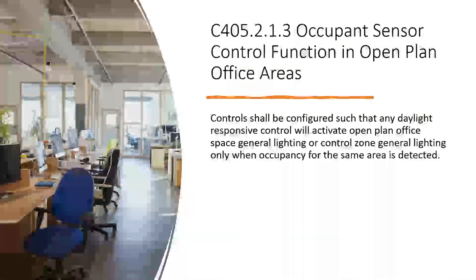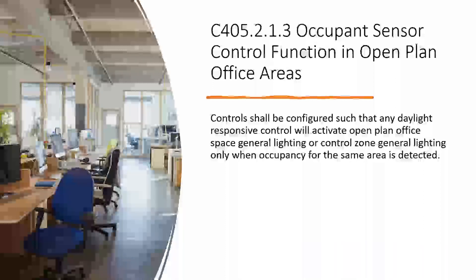Controls shall be configured such that any daylight responsive controls will activate the open office space general lighting or the control zone. Daylight harvesting takes precedence over the occupancy sensor — if the occupancy sensor is only allowed to turn it to 50% but the daylight photo control says we only need 30% output to meet the required illumination level, it's going to stop at 30%. It won't go to 50%.